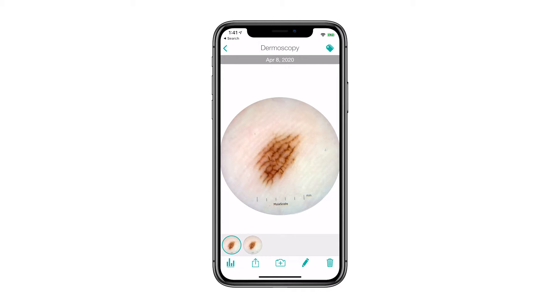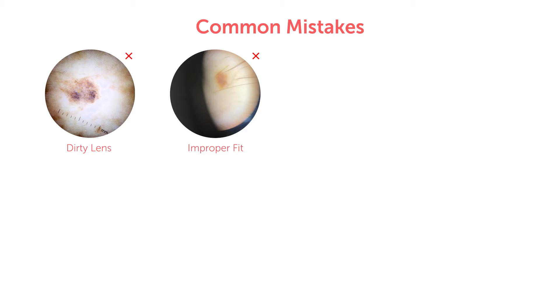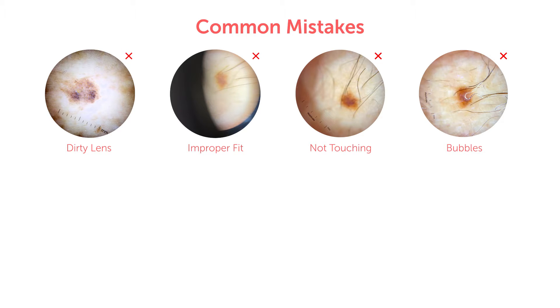Please do not send a blurry image because it will increase wait times and be unusable by the clinical team. There are a few common mistakes to avoid when taking dermoscopic images. The phone camera lens or Molescope lens may be dirty, resulting in a blurry image. The Molescope may be fitted improperly to the phone so the lenses don't line up. The Molescope contact cap may not be contacting the skin, or alternatively it is pressed too hard. Simply rest the contact cap on the skin and ensure it fully touches the lesion. If you're using fluids such as gels or rubbing alcohol, make sure that there are no bubbles over the lesion.